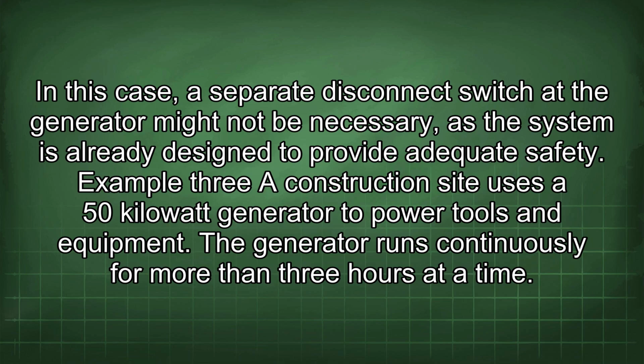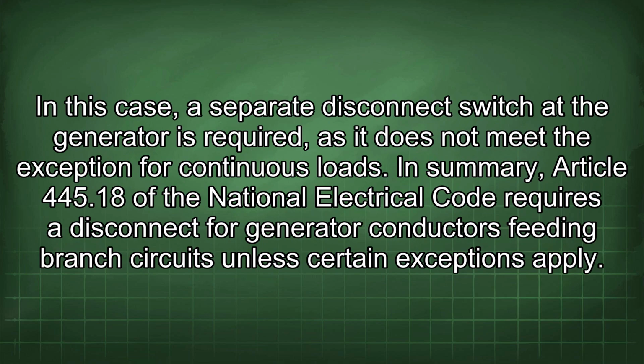Example 3. A construction site uses a 50 kilowatt generator to power tools and equipment. The generator runs continuously for more than 3 hours at a time. In this case, a separate disconnect switch at the generator is required, as it does not meet the exception for continuous loads.